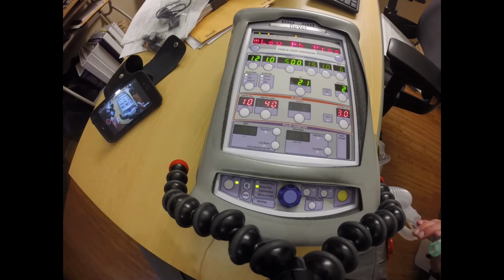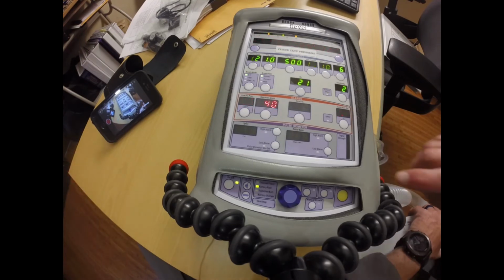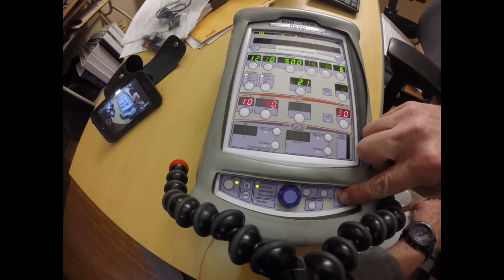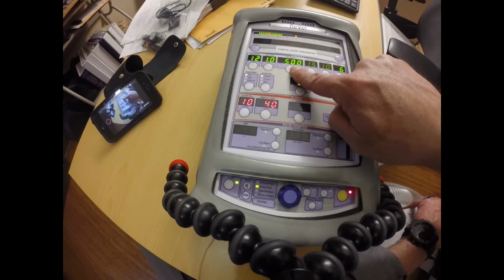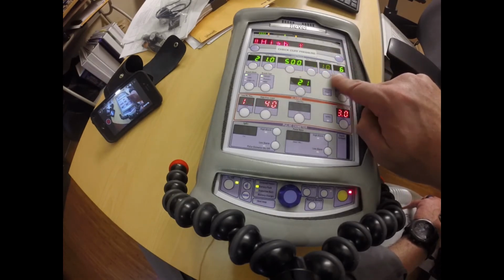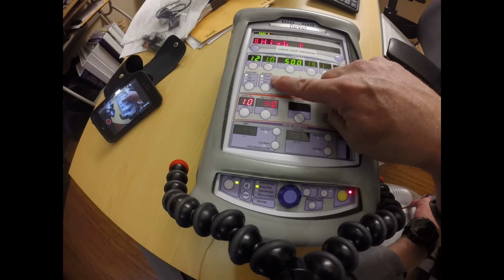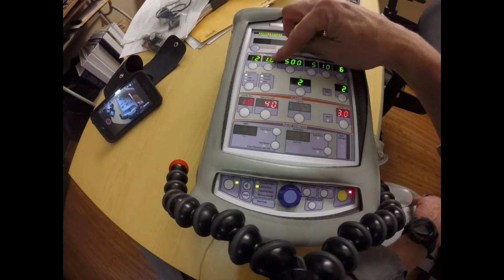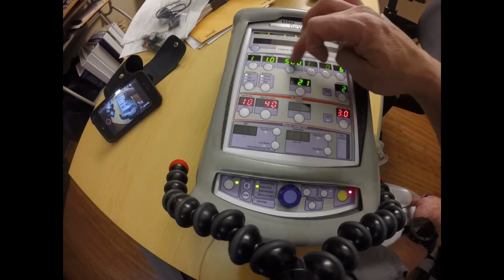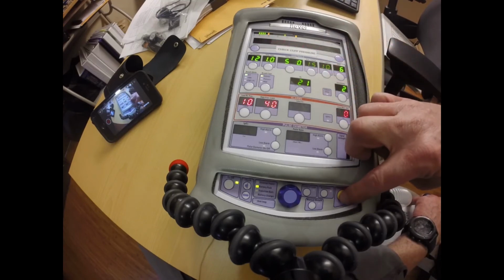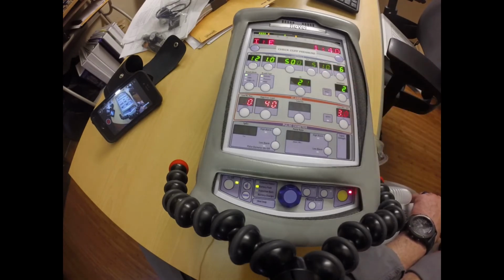When I pop the intubated patient up, it's going to give me some general settings. So you can see here that I've got a breath rate of 12, an I time of 1, tidal volume of 500, and a PEEP of 6 with an FiO2 of 21% and a sensitivity of 2. I'm currently in a breath type of volume and assist control mode. All the things that are highlighted or bright are what is in play currently. The things that are not highlighted or less vibrant are not currently in play, and so there's my control panel.